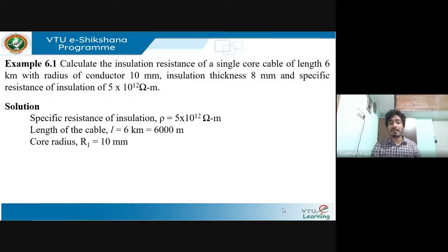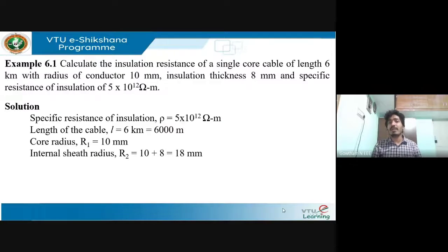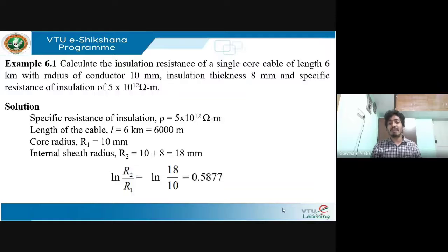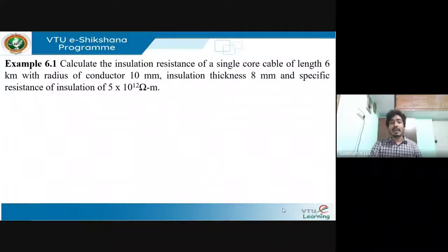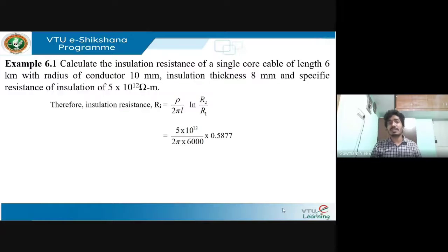Core radius r1 = 10 mm. The sheath radius r2 = r1 + insulation thickness = 10 + 8 = 18 mm. Therefore ln(r2/r1) = ln(18/10) = 0.5877. The insulation resistance expression is: Ri = ρ / (2πL) × ln(r2/r1). Substituting all values, the insulation resistance of the single core cable is approximately 77.94 mega-ohms.